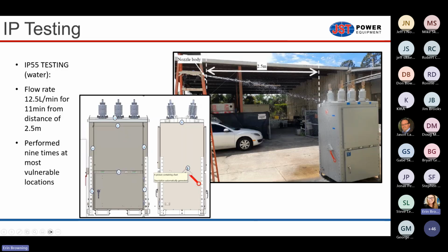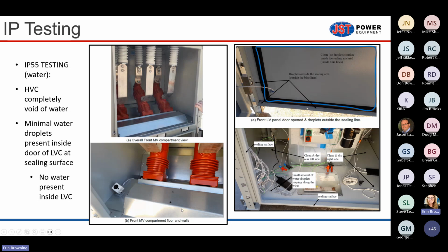Similar for the water test for IP55, we shoot it from 9 different locations, and the most vulnerable locations of the breaker: the roof, the front, the side. At the end of the water test, there was virtually no water inside the breaker. Again, customers are usually very impressed by this. FP&L in Florida were so impressed, they ordered a breaker from us. So I'll talk about that in a minute too.